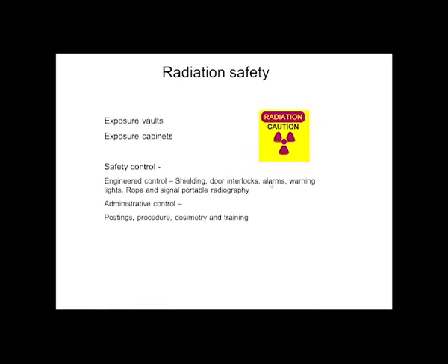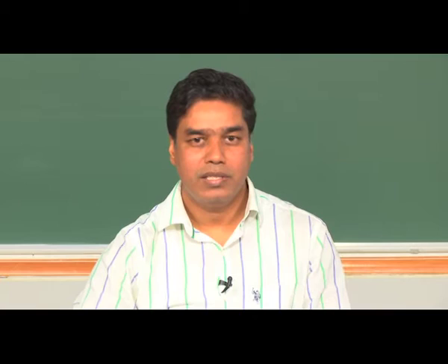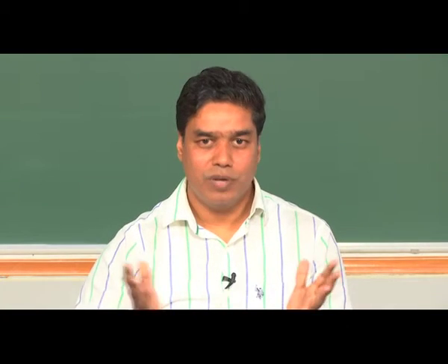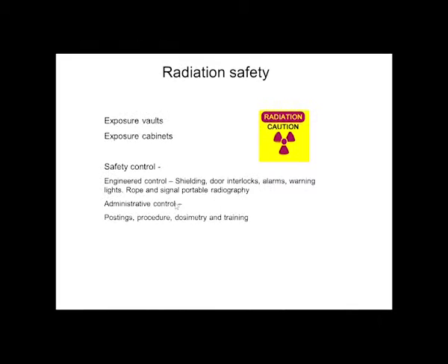Okay. So, that is about alarms and warnings, which come under engineered control with regard to safety against X-ray radiation. And if you are working on a site where you have open exposed areas, then around that exposure area, since you do not have 4 walls, an enclosed room, you should first of all use ropes around it to prevent people from going around that area.